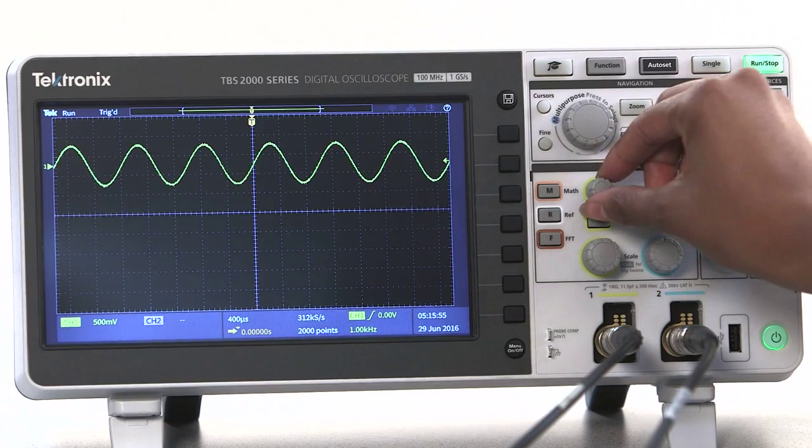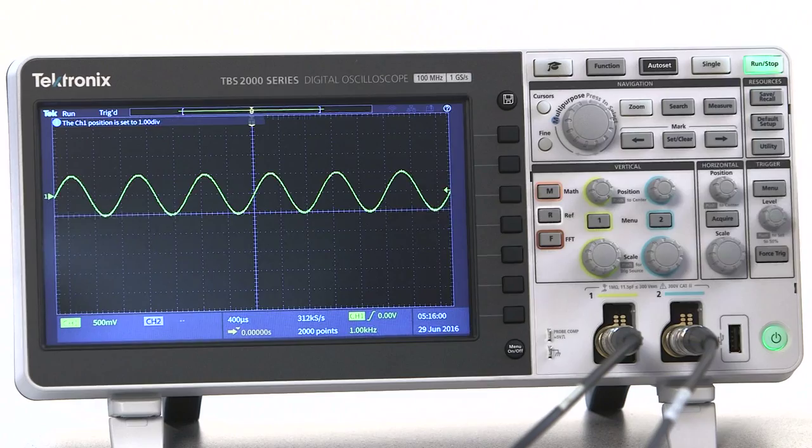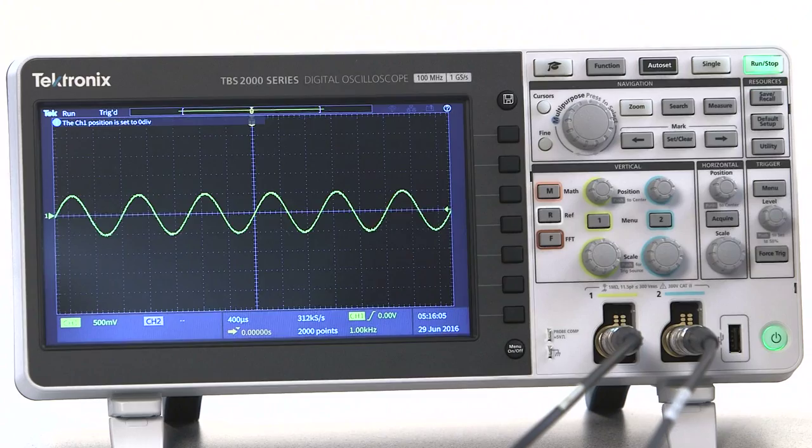The vertical position control moves the waveform up and down. Pushing the knob brings the baseline back to center. The channel menu buttons turn the channel on and off, and also open up the channel menu.